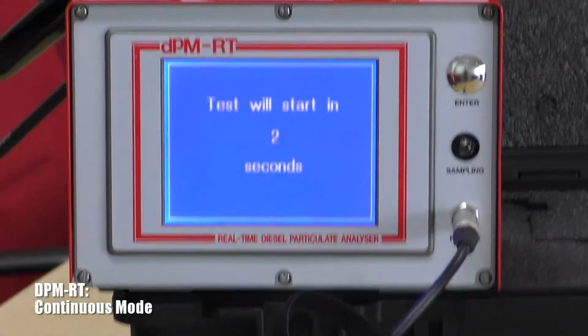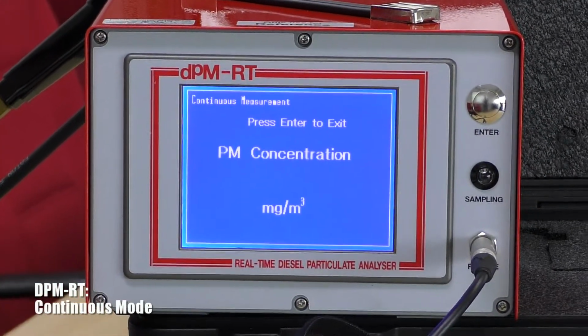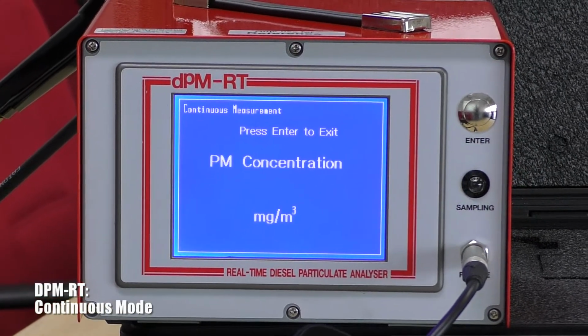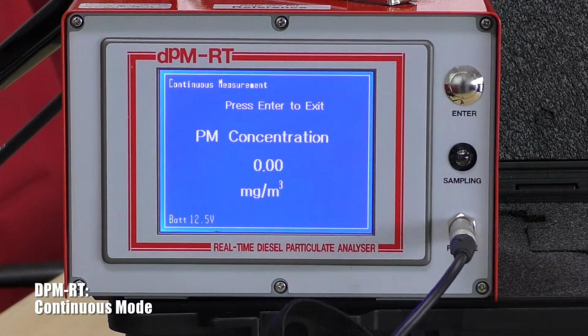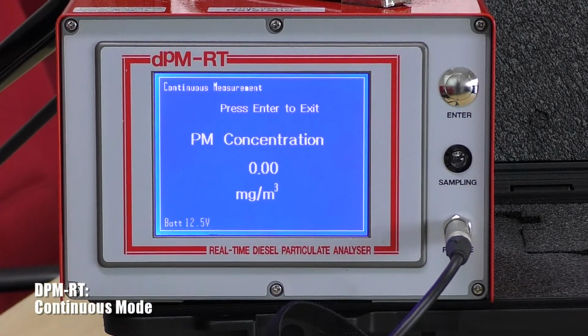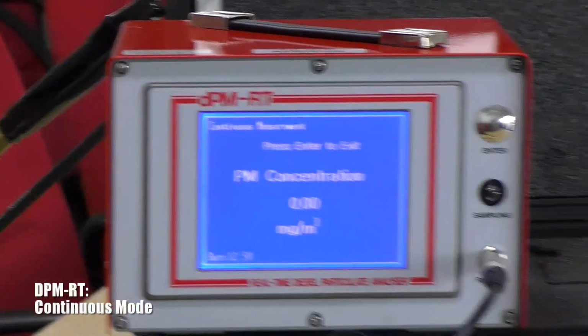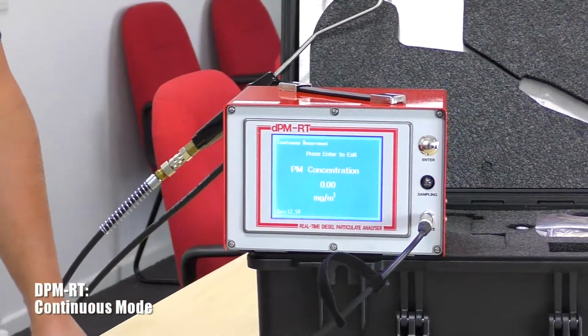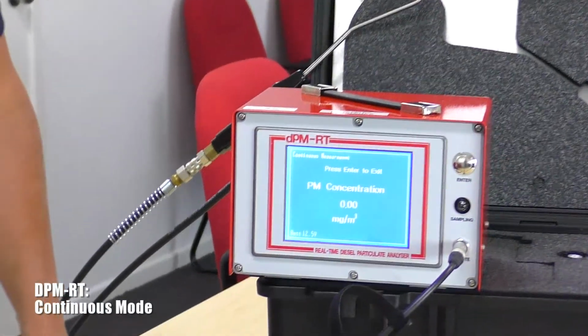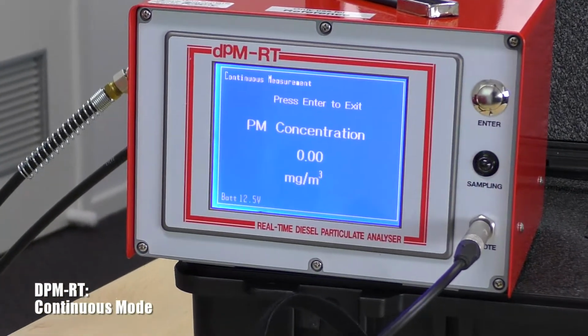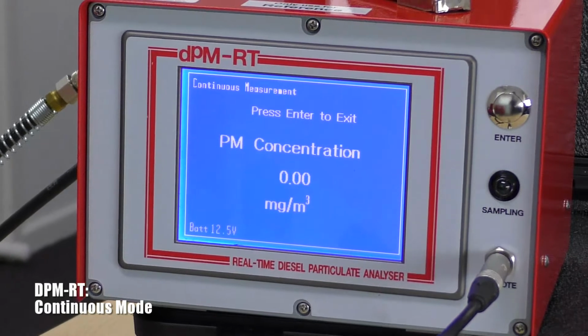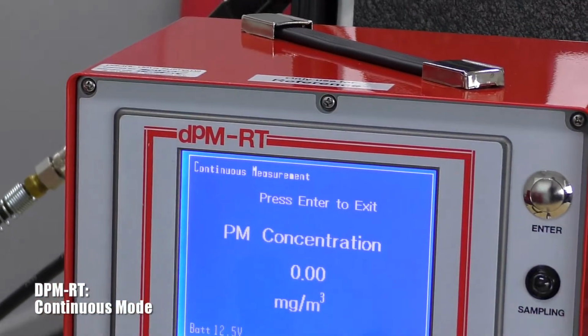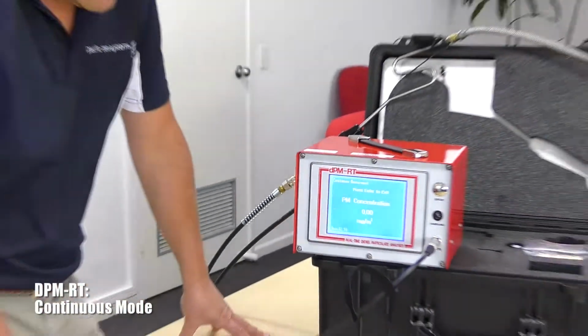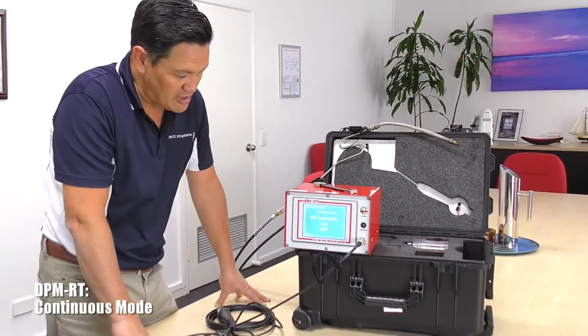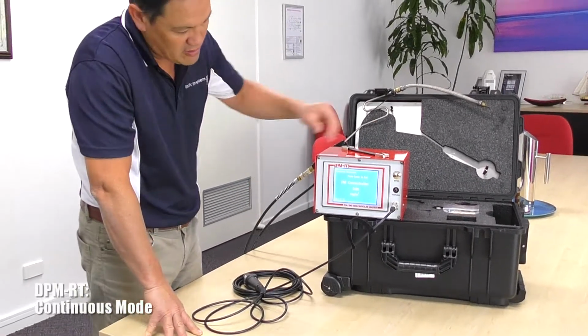The test will begin in 5 seconds as per the countdown timer, and the instrument is going to continually monitor the concentration in milligrams per cubic metre, reference to elemental carbon again. You'll notice that there is a bit of a lag in displaying the value of milligrams per cubic metre because it is conducting a number of averages prior to displaying the value on the screen. When you want to exit the continuous measurement mode, select enter.